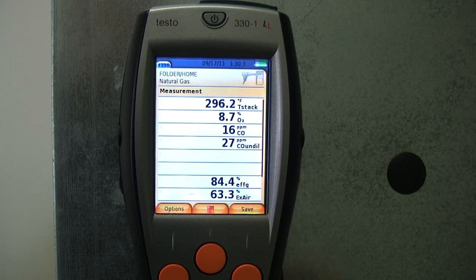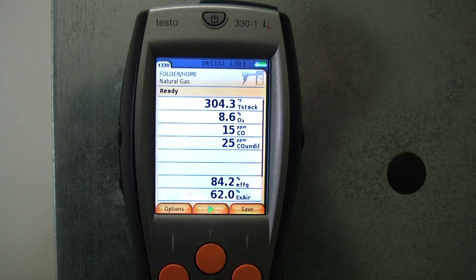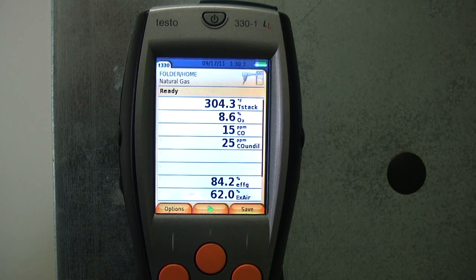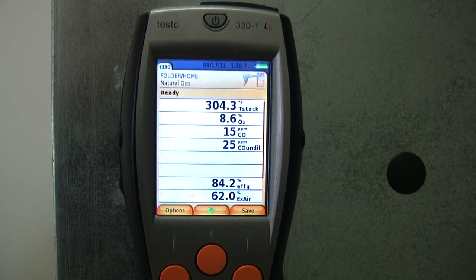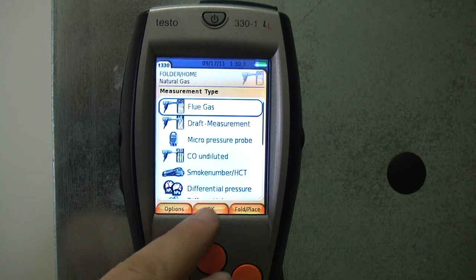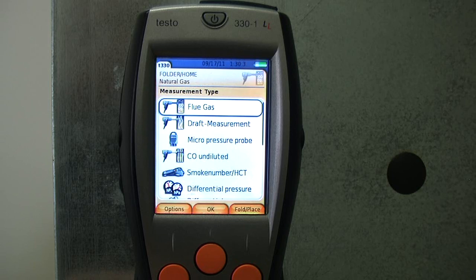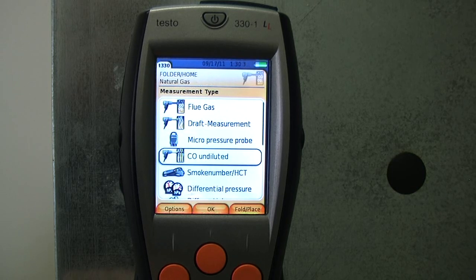Alright, so after we're certain that there's no leaks in the heat exchanger, I'm going to go ahead and stop it. Now we're going to do a draft test. So I'm going to kick my burners back off, overheat the house, don't fall off, it's going to shoot me. I'm going to hit escape. Alright, what I want to do now, you know what, let's go ahead and do our gas, make sure the gas pressure is set right.